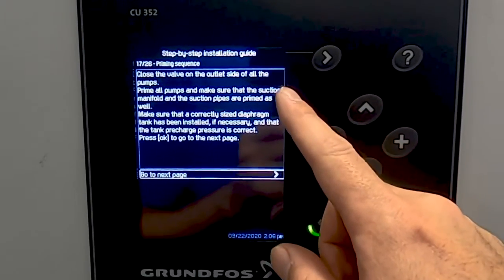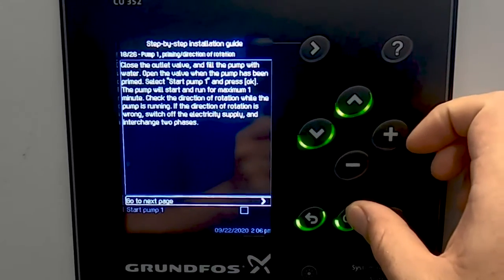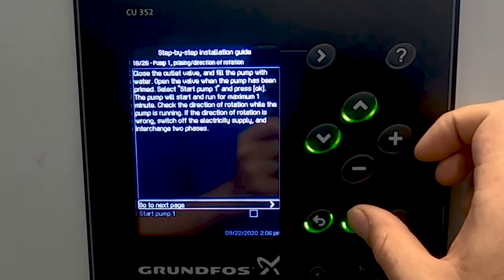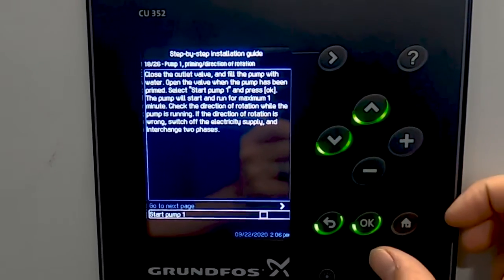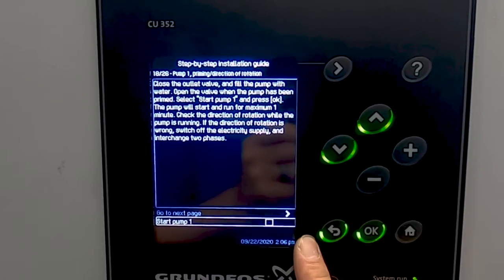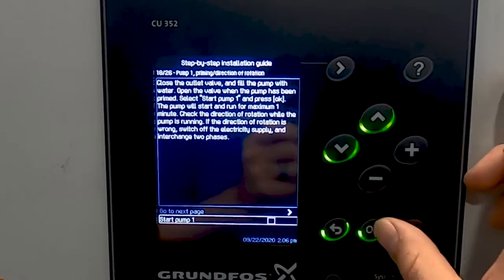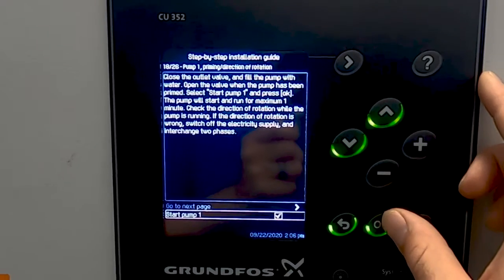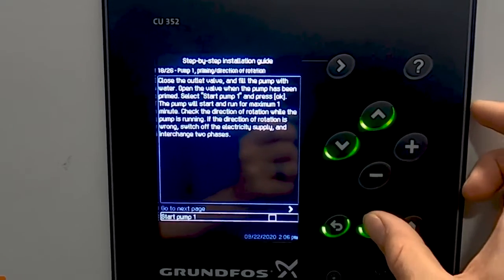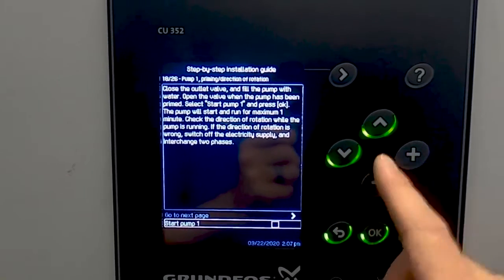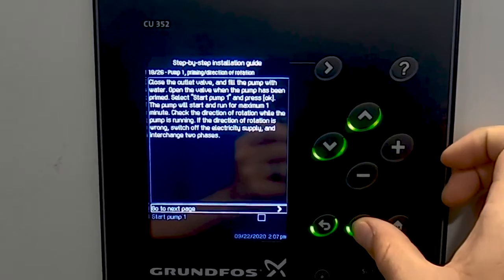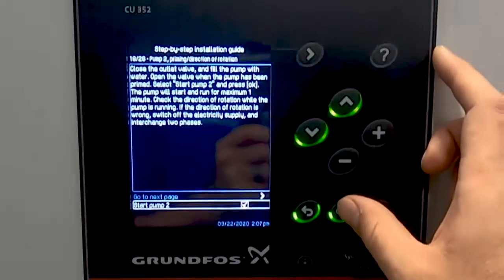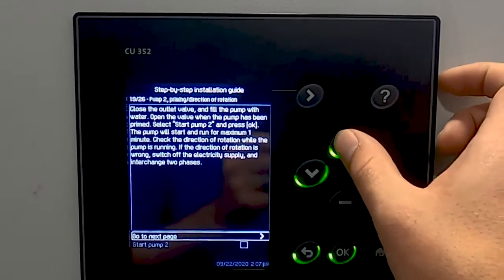We've already done the priming of the pumps, but this is another step to make sure they're completely vented — it will actually operate the pump. Make that vent finger tight and have someone near the pump. Also, these pumps will run at full speed, so you may need to close the discharge valve just a little bit so you don't have the full system pressure. From here, we're going to start the pump — this is a good time to get any air out of the system. You hit OK, start the pump, and then again to stop the pump. Repeat this one by one until all the pumps have been vented and primed.